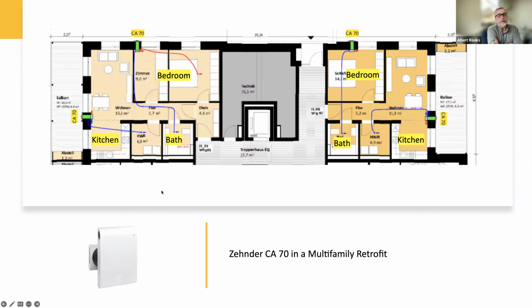And so here's what it looks like in their basic training videos. I don't have any pictures of our installations in this case. But we take a look at that upper left-hand corner where it says CA70, we got that green thing. So that green thing is basically the tube that's going through the wall. We drill a 12-inch hole through the existing building, and we slide a tube in it. And inside that black tube, you can kind of see the picture of the unit down in the bottom of this slide. And it's got a white cover. That's where the core is. It's got the round circle on the left-hand side. That's where the airflow comes out or goes in. And then that black tube is basically 12 inches long at minimum, and it's 12 inches in diameter.